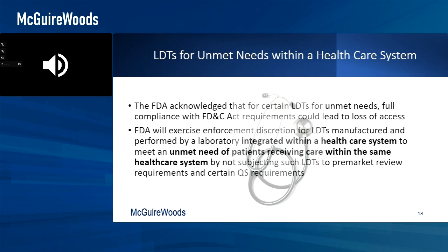So FDA is going to exercise enforcement discretion for LDTs that are manufactured and performed by the lab integrated within the healthcare system to meet the unmet need of patients receiving care within that healthcare system. So kind of tricky. It needs to be basically the hospital or the health system lab that has developed this test and is meeting an unmet need, which has to do with rare disease, and we'll get into on the next slide sort of what qualifies as unmet need.